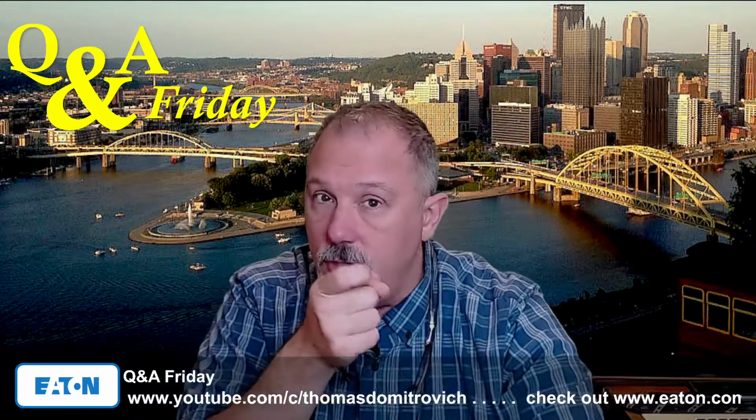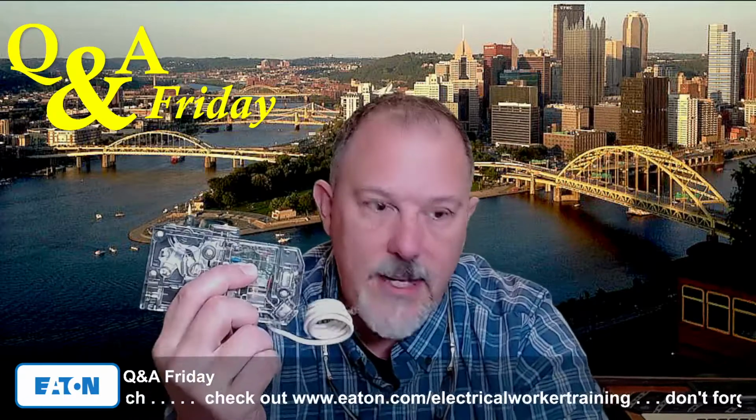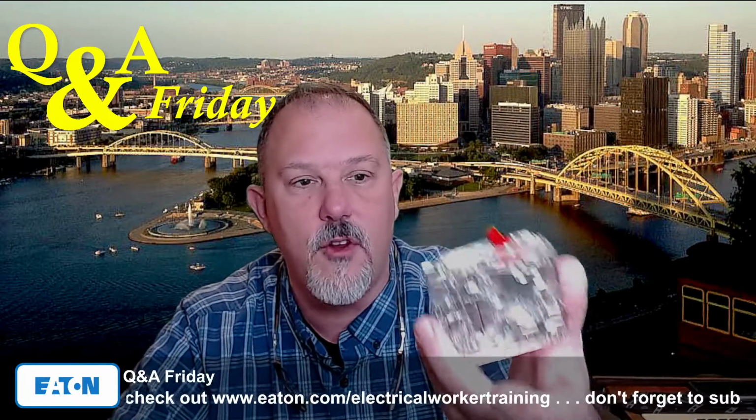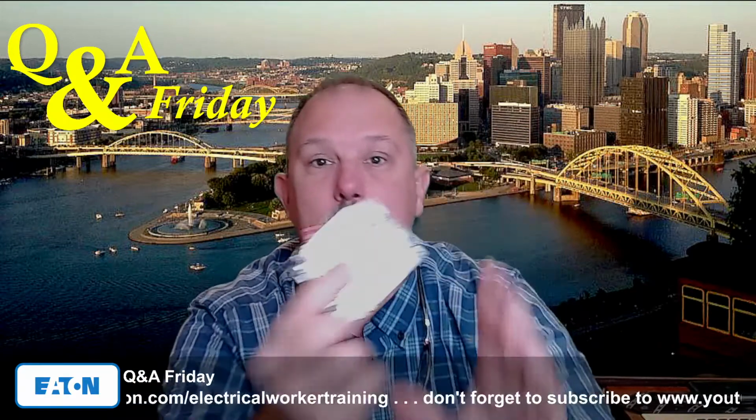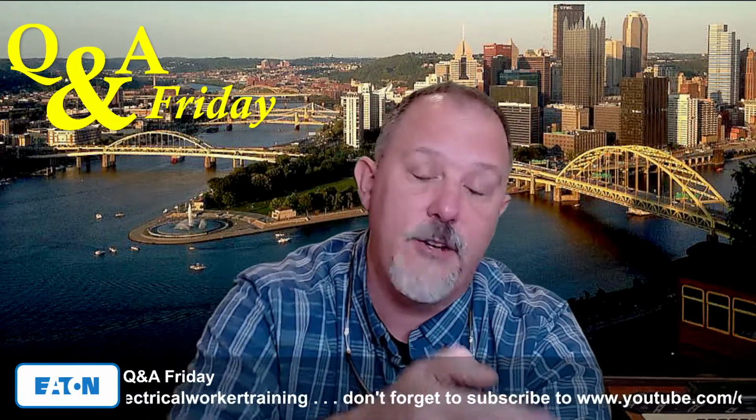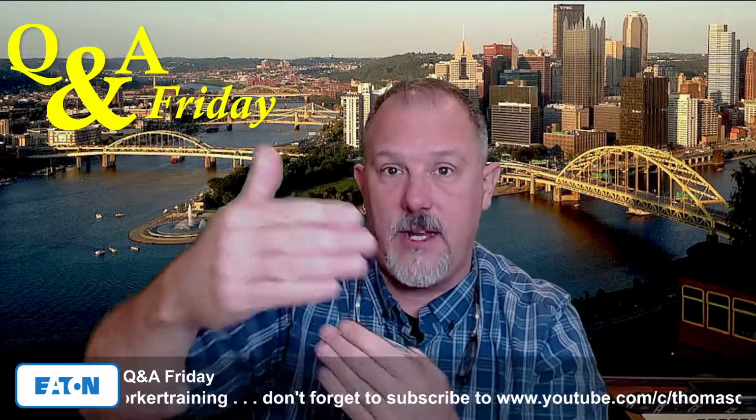And so people would use an infrared gun, and they would look at the face of these breakers. If it was an AFCI circuit breaker, that conductor is right there at the front. If it's a standard thermomagnetic circuit breaker, that little conductor is back here in the middle of the circuit breaker, so it's not near the front. It has a little bit of time for the heat to dissipate and not heat up one specific spot on the circuit breaker.